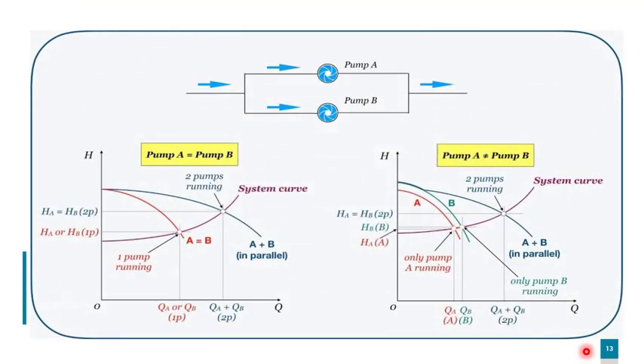In the parallel pumping system configuration, we have two options. Either both pumps are the same in characteristics, that means pump A is the same as pump B in flow and head. In the second configuration, pump A is different from pump B in their characteristics. That means the head and the flow are totally different for both of them. So we can see the difference in the system curve for both cases.